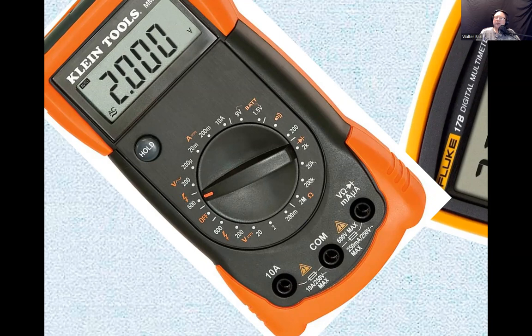So if you have current going through the circuit that is, let's say, 3 amps, you would not be able to measure that if you select this range, because this range can only measure current up to 200 milliamps. If you have 3 amps going through the circuit, you'd have to select the next bigger range, up to 10 amps, and 3 amps fits within that.